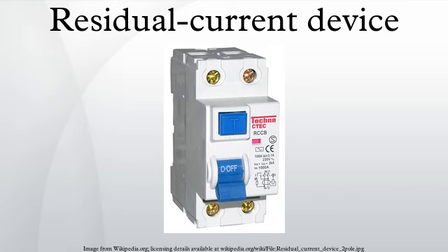GFCI devices approved for protection against electric shock trip at 5 mA within 25 milliseconds. A GFCI device which protects equipment is allowed to trip as high as 30 mA of current. This is known as an equipment protective device. RCDs with trip currents as high as 500 mA are sometimes deployed in environments where a lower threshold would carry an unacceptable risk of accidental trips. These high-current RCDs serve for equipment and fire protection instead of protection against the risks of electrical shocks.